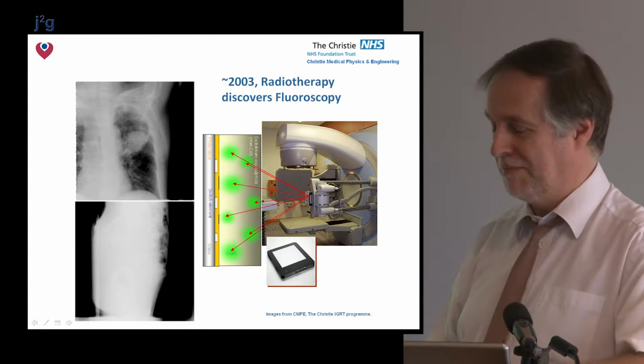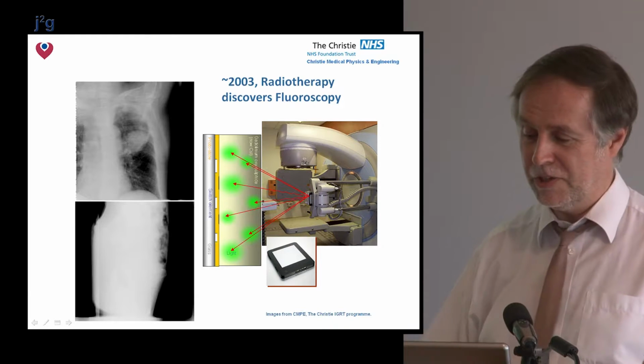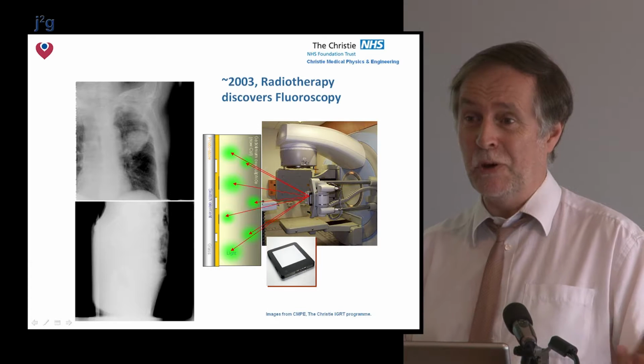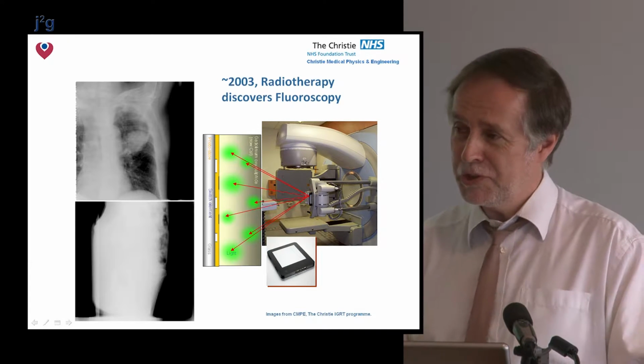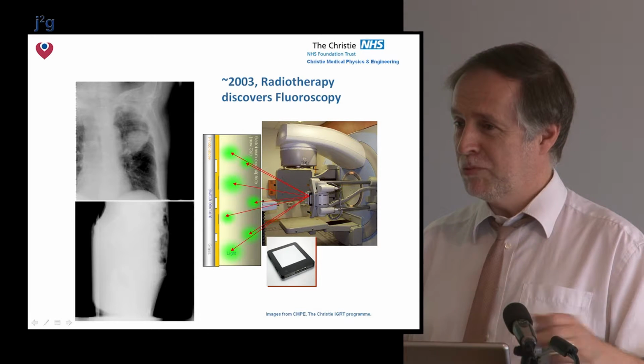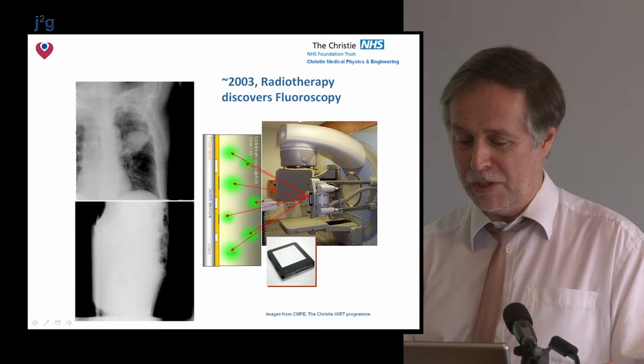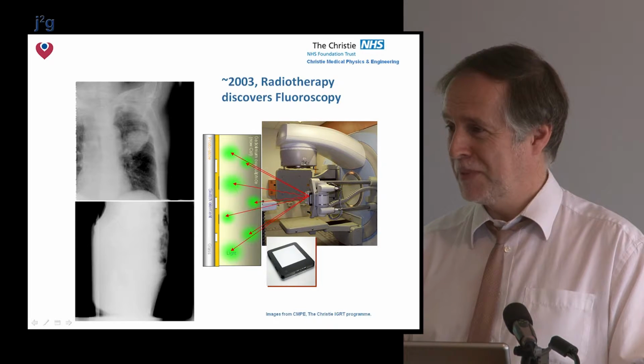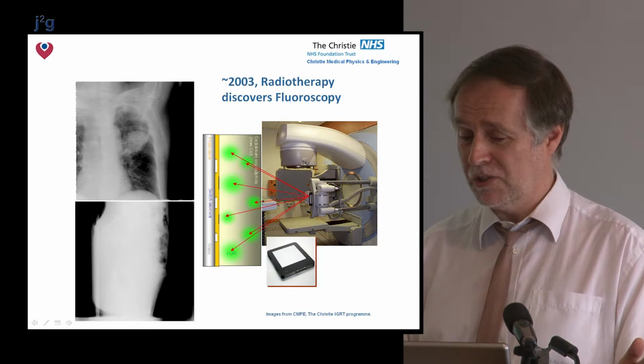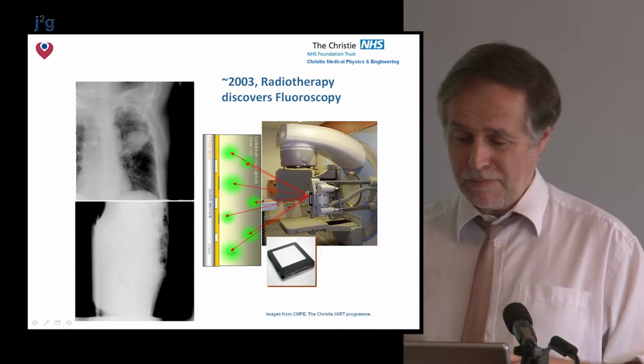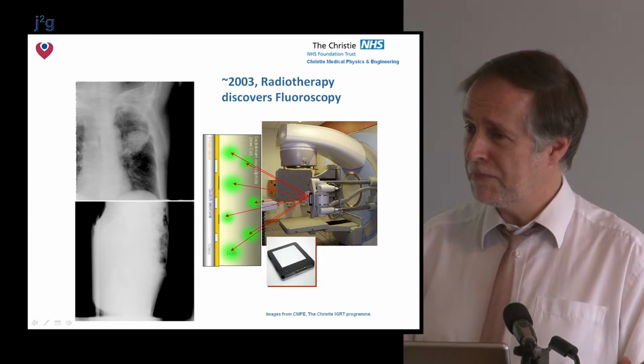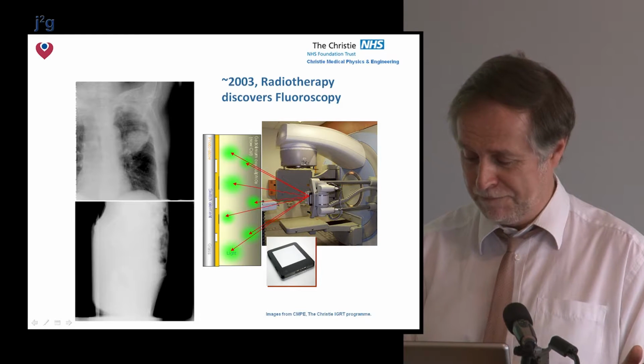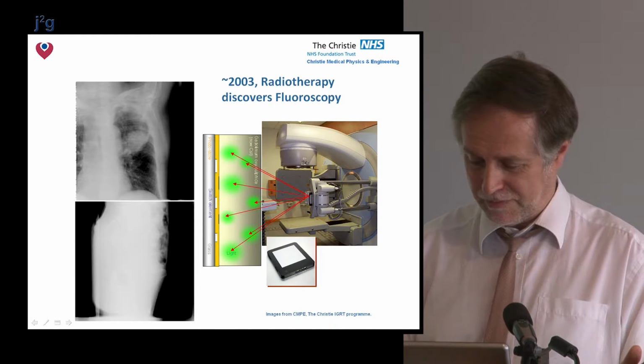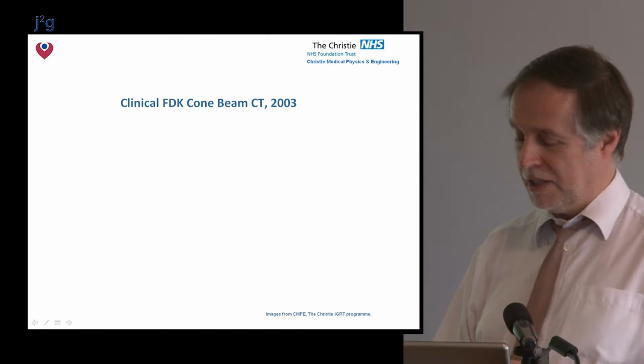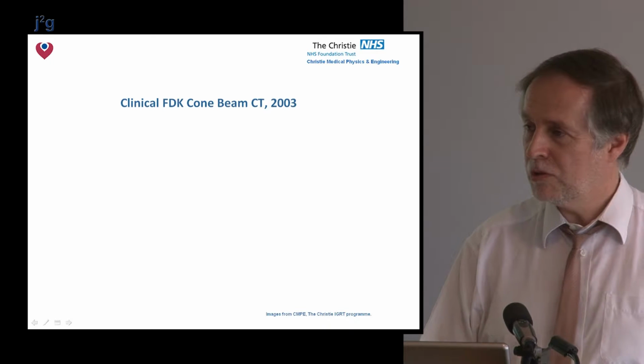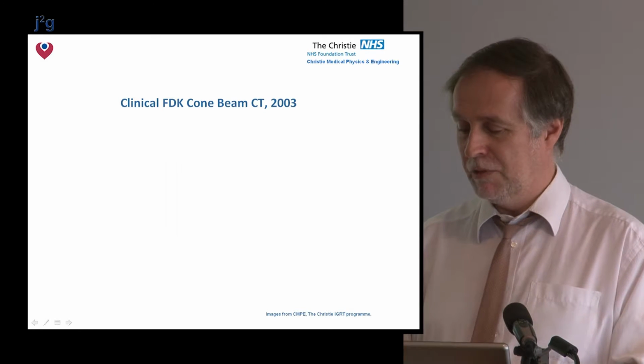If you actually rotate our X-ray tube, which is strapped onto this linear accelerator gantry, around the patient and keep it on, you can see that we can get a rotation fluoroscopy sequence. And you can probably see that that patient was keeping perfectly still, but they were not actually keeping perfectly still. They were jiggling around. That's natural physiological motion that you just simply can't stop. And at this point, we got involved in another project. Fluoroscopy was one thing. We could take some X-ray pictures of our patient, which was fine, but it would be a lot better if we could actually do something far more exciting and introduce what was called cone beam CT imaging.